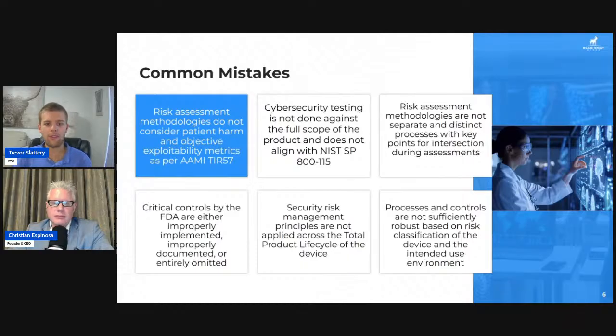Another common issue that we see is risk management principles not being applied across the total product lifecycle. Now, cybersecurity is a very unique type of testing. It's a very unique part of the submission since it's largely exploratory as opposed to testing against a benchmark. For emissions testing, for your 60601 testing, you're saying there's a threshold. This level of emissions is intolerable. This level is acceptable. This level of EMC interference is intolerable.